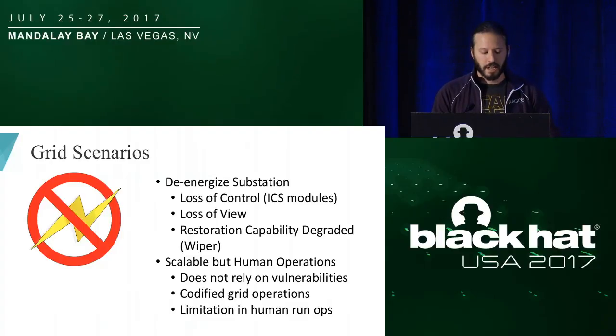In addition, as Robert was outlining, the wiper functionality isn't just impacting the SCADA software, but it's impacting the configuration files for all these devices. You saw screenshots of the Siemens gear, the ABB protective relays - those configuration files loaded in there, instead of going after Word documents, Excel documents, or Access documents like a traditional wiper, it's going after those configuration files, hampering the actual restoration of this equipment and delaying the return to service.